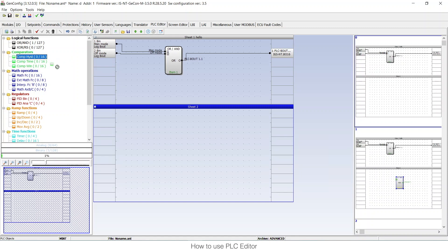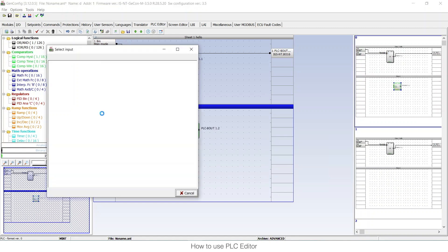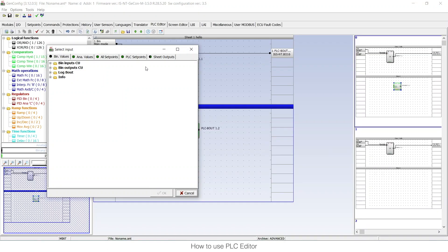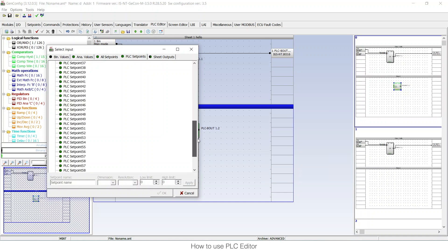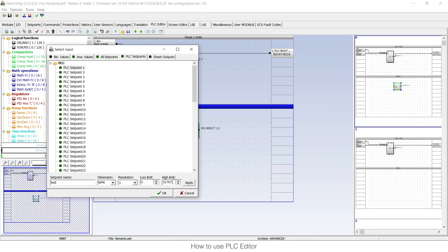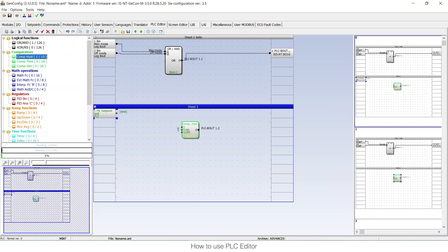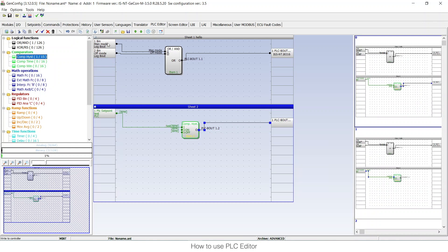The last thing I want to talk about is PLC set points. I'll create a simple logic to show you. PLC set points is a function in Comap where you can add set points under PLC — there are a total of 64. You can configure each set point with the parameters you want: give it a name (for example 'test'), choose units (for example rpm), set the resolution, and limit the values — for example between 0 and 2000. Press Apply and connect it to show how analog values look in the PLC monitor.